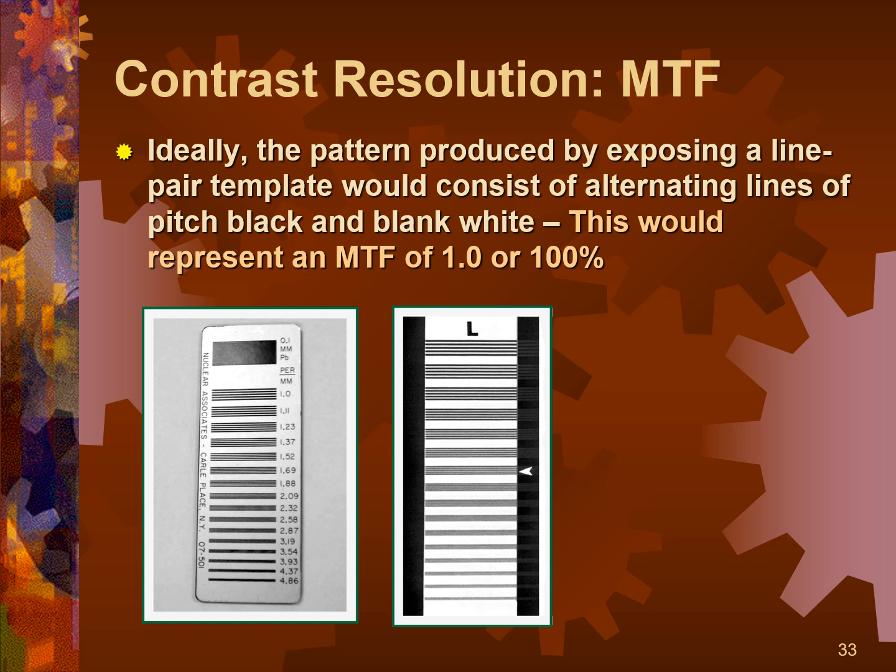So we have a line pair test tool. Okay? And then we have an image of the line pair test tool. By visual inspection, if we actually have this line pair test tool and we're holding it in our hands, we can see that it is a sheet of polymer plastic and it has metal strips embedded in it, so that it has an alternating pattern of highly attenuating material or radiopaque material, radiolucent material, radiopaque material, radiolucent material.